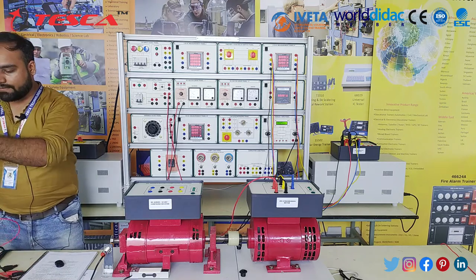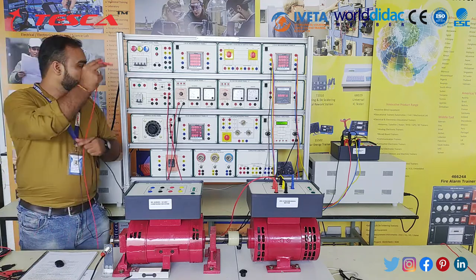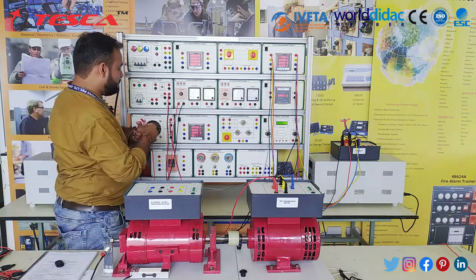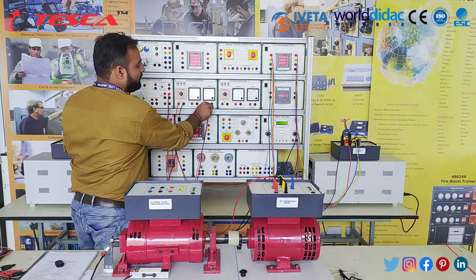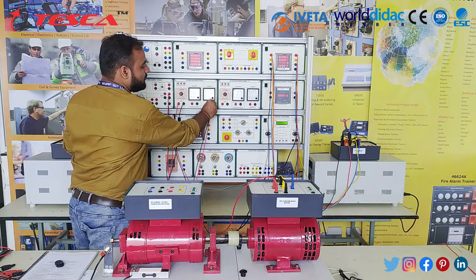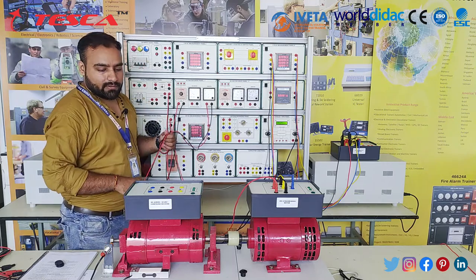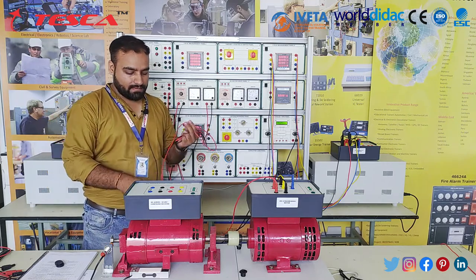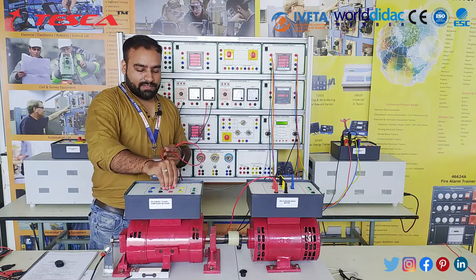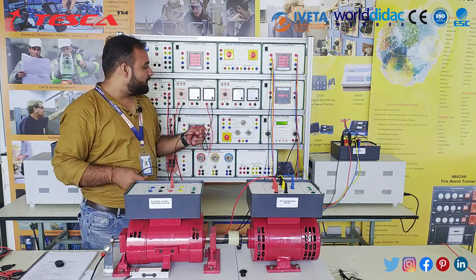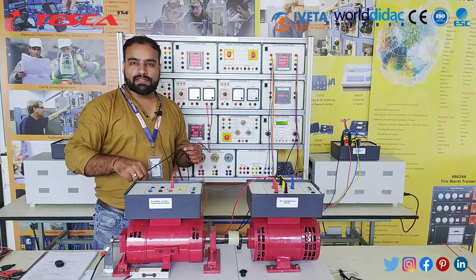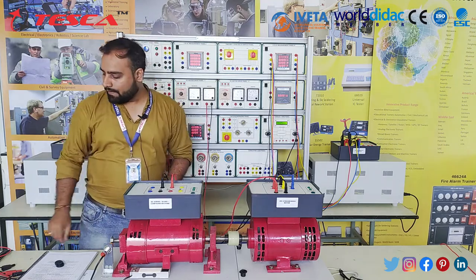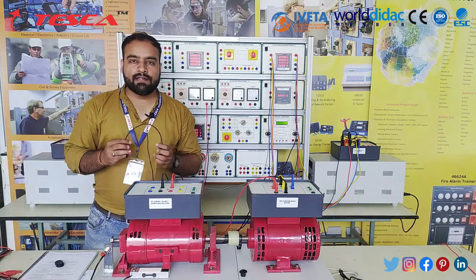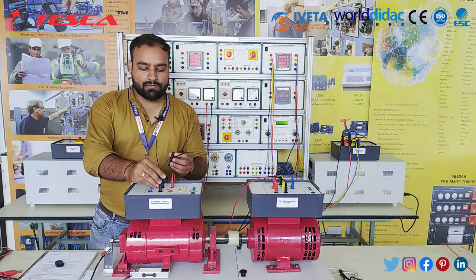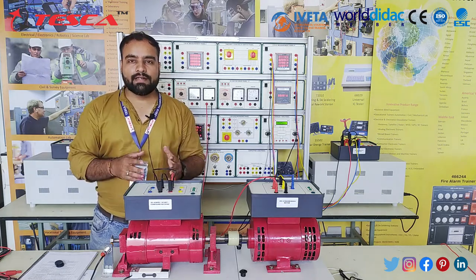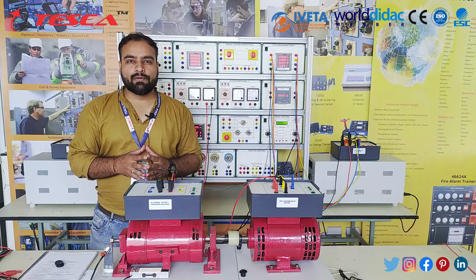and then we will connect the armature output T5 and T6. T5 will be connected to A1 of the armature coil, and T6 will be connected to S1 of the series coil. Now, using a short link, we will short S2 with A2. Here, our series connection has now been completed.